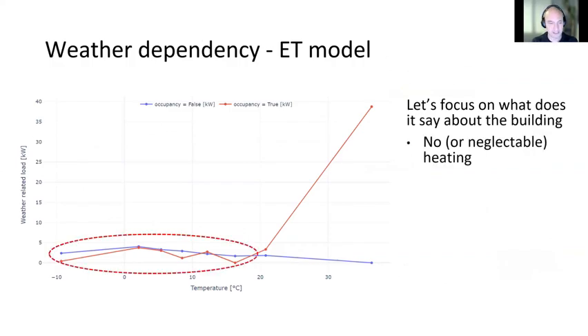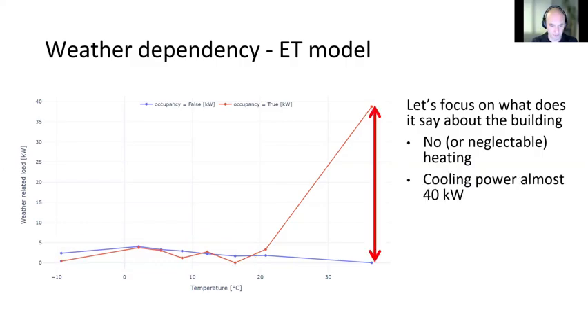First of all, during cold temperatures there is almost no increase in energy consumption, so we can say there is no, or very low, negligible electrical heating. But we see a very sharp increase in energy consumption with hot temperatures, like 100 degrees Fahrenheit, where we see the arrow, and there's almost 40 kW for cooling.